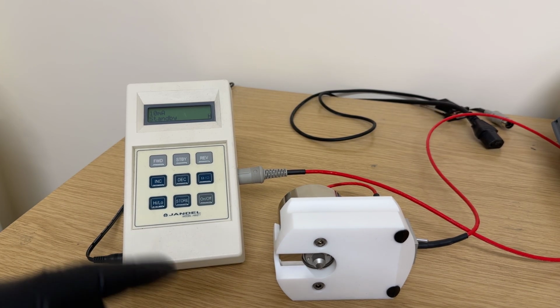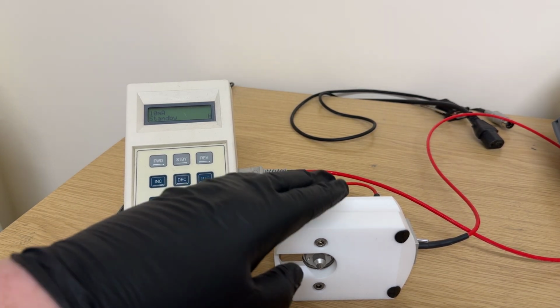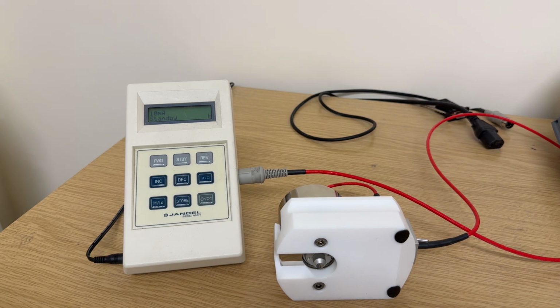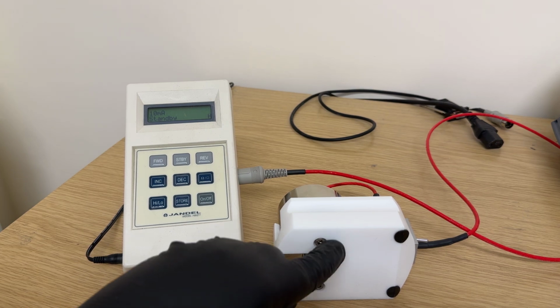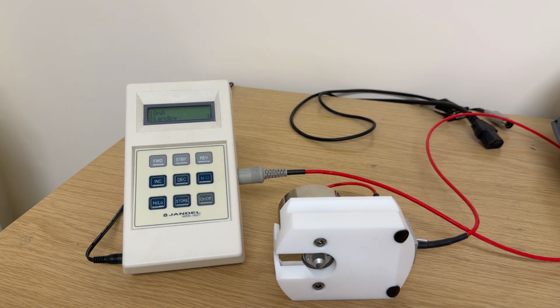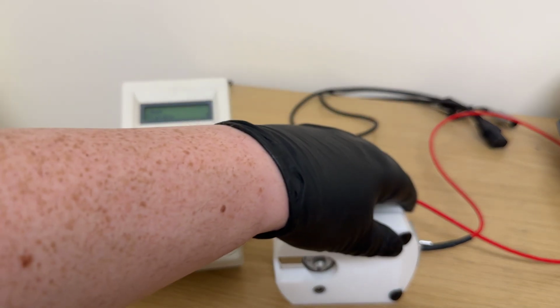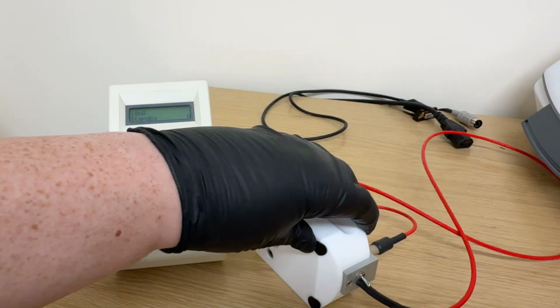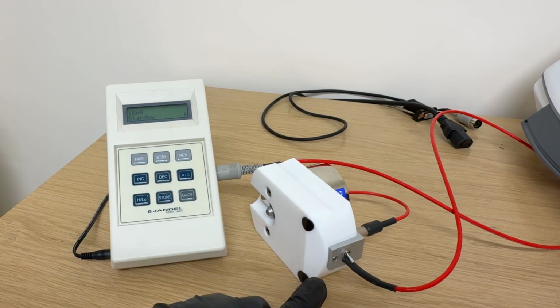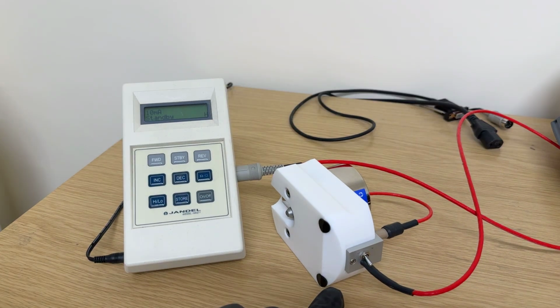Here we have the HM21 test unit and the hand applied probe. When the probe is correctly positioned in the hand applied probe, the needle should be in line with the two outer screws. At the back of the hand applied probe is a switch. This is an interlock switch to prevent flow of current. At the bottom position, it's in S, which is for short. That means the current can't flow through the probe and into the sample.